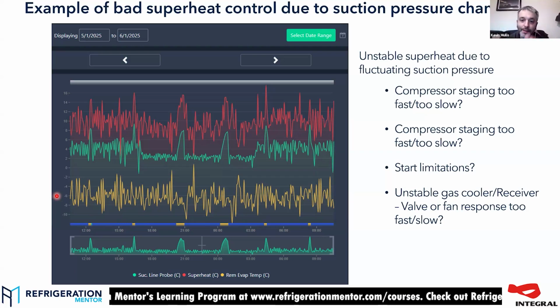is doing. The last one I put on there is CO₂ specific. How's the gas cooler doing? How's the receiver doing? Flash tank, as some of us will call it. The other thing that affects suction pressure on a CO₂ system is what those two valves are doing, because ultimately pressure in the flash tank or receiver ends up being pushed down into the suction. And if you are up and down and up and down on how things are feeding out of the gas cooler and how things are feeding out of the liquid receiver into the suction, you're going to send the suction pressure crazy, regardless of what the cases are doing.